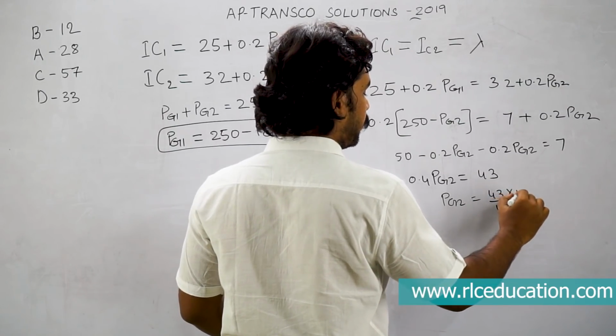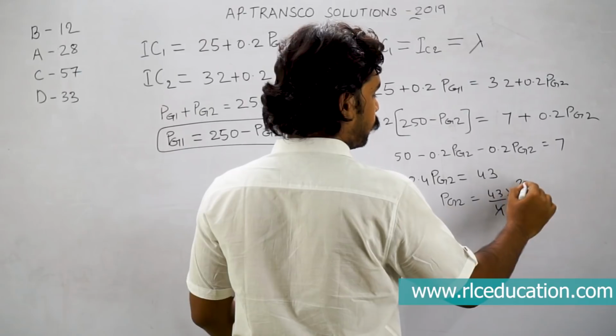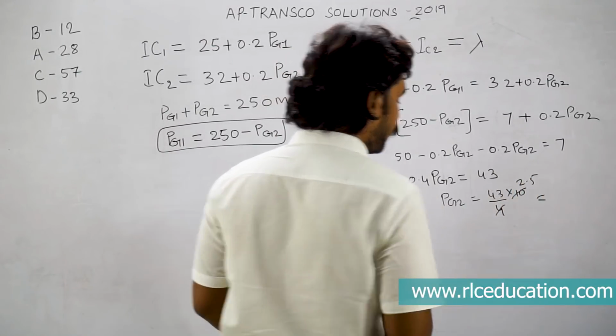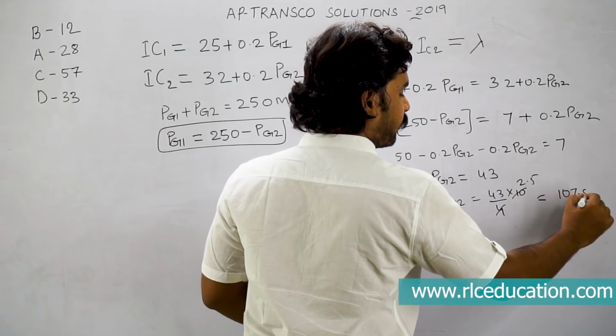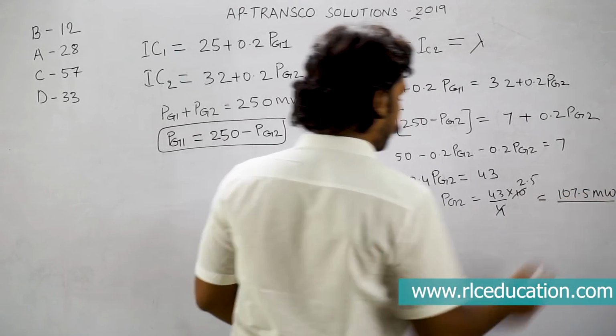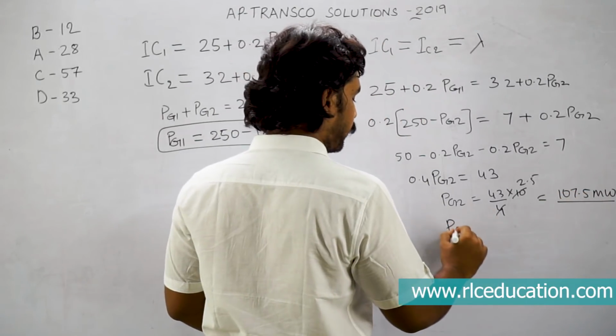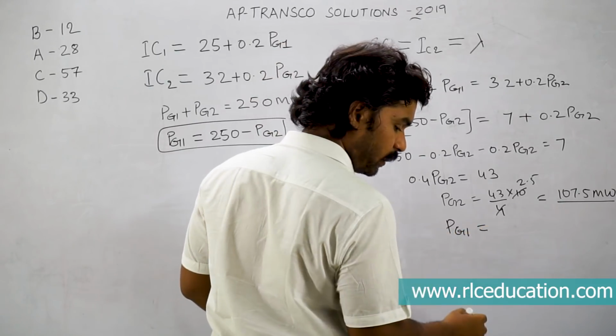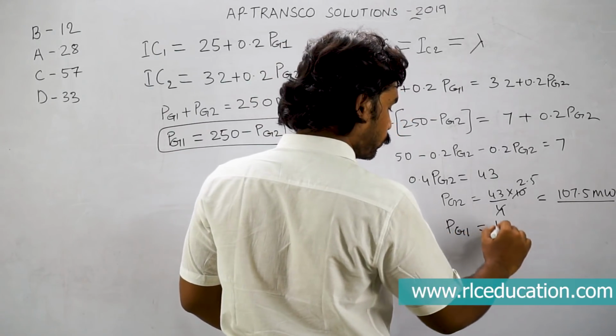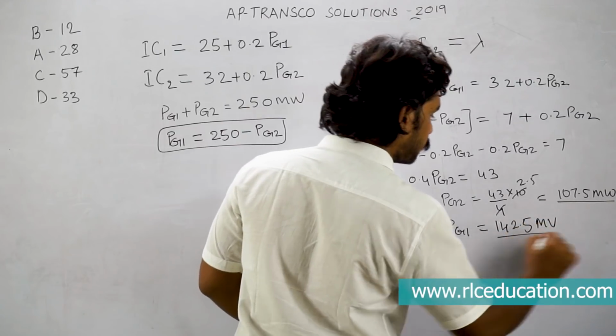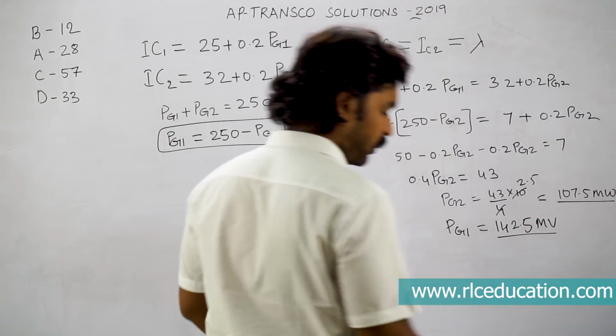I can write that as 4 by 10 also. So 4 ones and 4 2.5. So 43 into 2.5, if you do it, gives 107.5 megawatts. So if PG2 is 107.5 megawatts, you can directly find PG1. PG1 will be 142.5 megawatts.